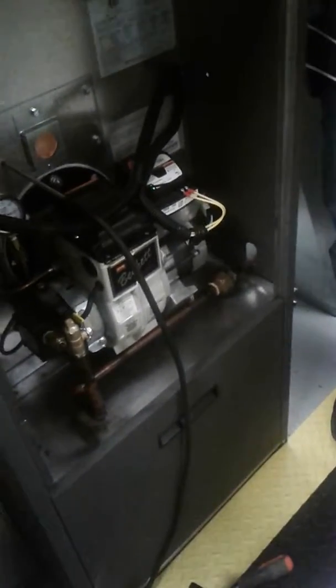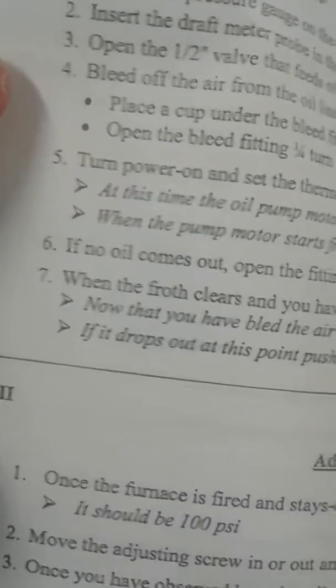Okay? Every time he holds that button in, the oil pump is spinning, pumping oil into the heat exchanger and not being burned off. What's happening is that when that oil gets inside that heat exchanger, it's going to burn up. Okay, catch fire a little bit. The first group that actually happened with, okay, it wasn't a big fire nothing like that, but it did. You could see a little bit of brighter yellow flame. Okay. All right. So now we're almost done here, guys. Okay, the furnace is running great. All right. Now it says the froth clears. Okay, we already did that. We're good, and the unit is running.